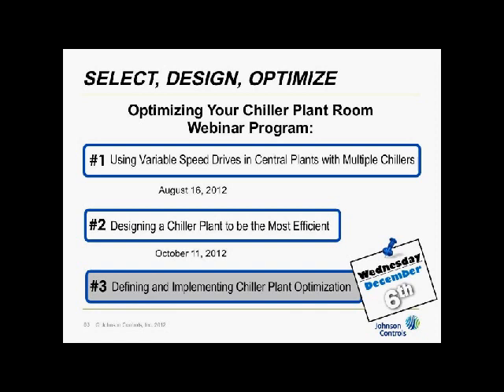Let me see what else. Can you use a Belimo PICCV pressure-independent automatic control valve? You can use pressure-independent valves, sure. The pressure-independent valves have value. The bigger question isn't so much, do they work, but whether they provide enough savings to justify the additional cost, because you usually have to have at least about 5 psi at the valve to make it work. So there's issues with it being a little higher in that respect, and then it saves in another respect. So it does save net overall, but does it save enough to justify the higher cost of today's valve? I'm not sure about that one. The jury's out.